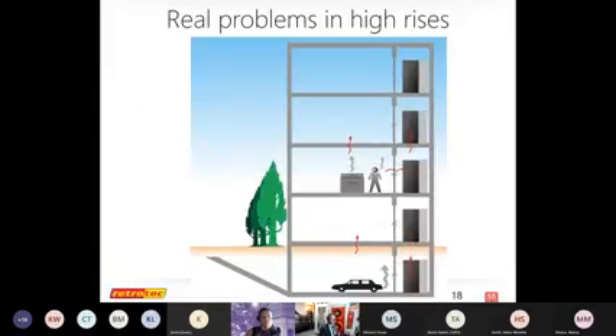And like I mentioned, the taller the building, the stronger the stack effect is. It gets that term from working like a smokestack or a chimney. The taller it is, the stronger it's going to be. The leakier it is, the stronger it's going to be. And so if you have a parking deck or something like that underneath, then you can be bringing in other things along with that air that you may not want to be breathing indoors. We don't really smoke inside anymore. It might be time to update that, but you can kind of see where this diagram is going.